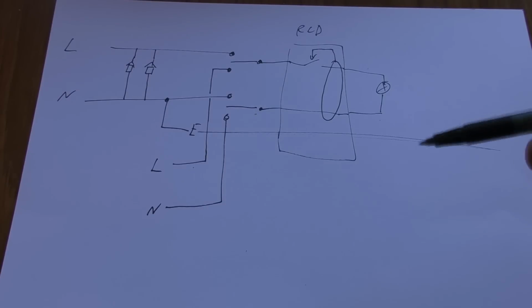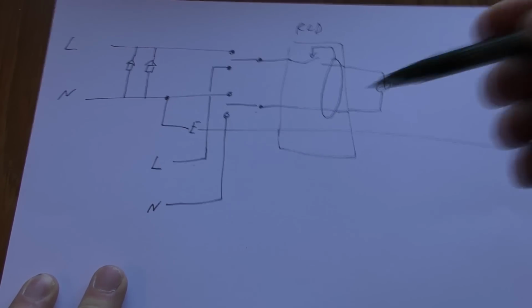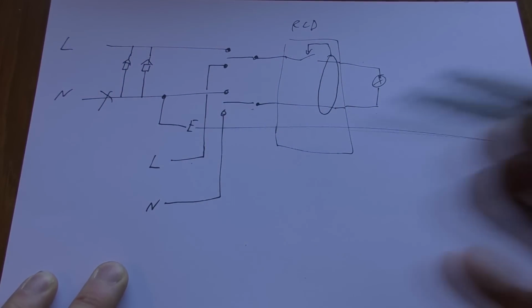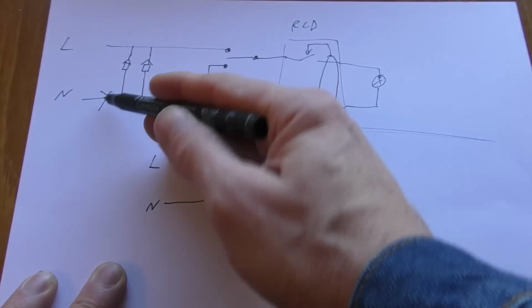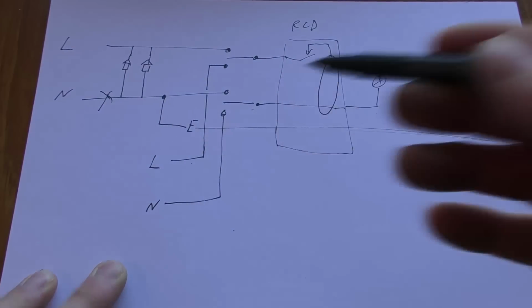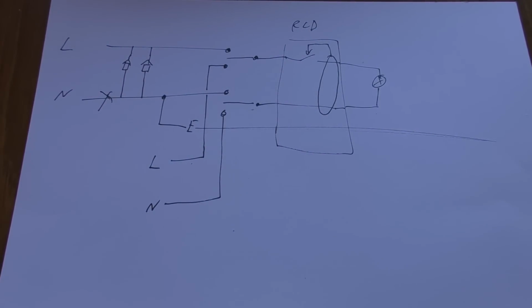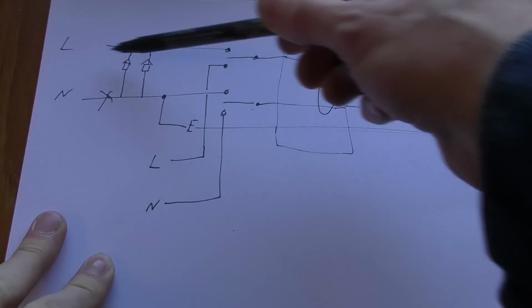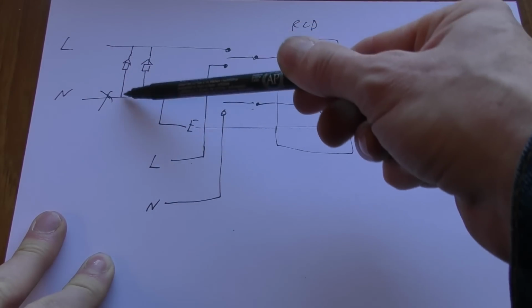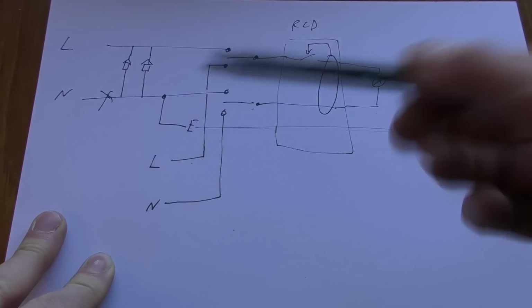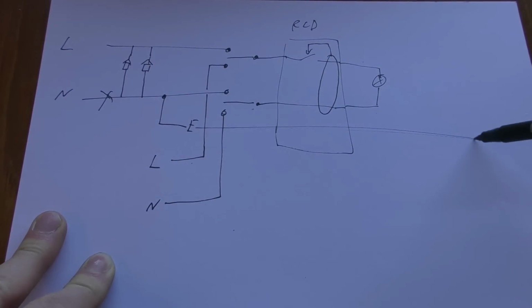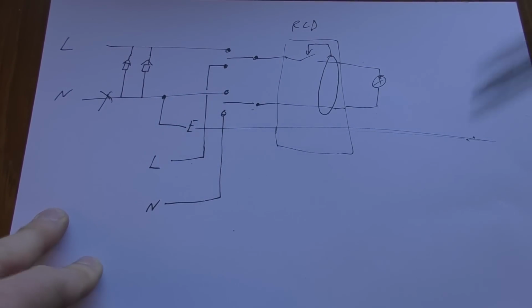But one potential situation you can have is if there's a fault in the street, and obviously if you have a power outage, that could be because there's a fault in the street. And let's say we have a neutral fault. This is generally regarded as a PEN fault, protective earth neutral fault. What effectively happens is that our live goes through the loads in the other houses, and effectively your earth that's distributed through the house is at mains potential.